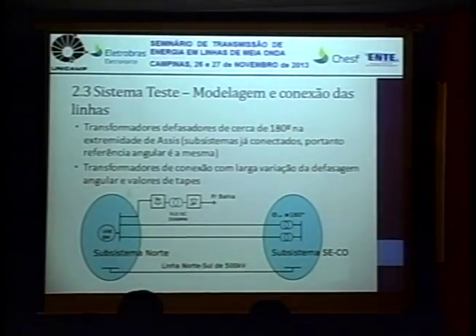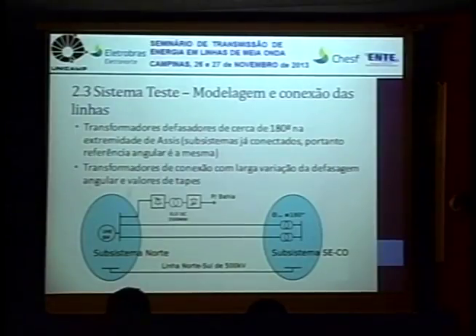And what did we use to try to improve these performance levels, more specifically in terms of losses, but also in the current profile and voltage profiles of the lines? So we needed to adjust the taps, controlling the voltage at the terminals, both in the input and output terminals. So we are working with this. This is not a new idea. This was presented in several half-wavelength papers. So working with transformers with a large tap variation, so we could have a broad control of voltage in the two terminals so as to keep the transmitted power close to the characteristic power.